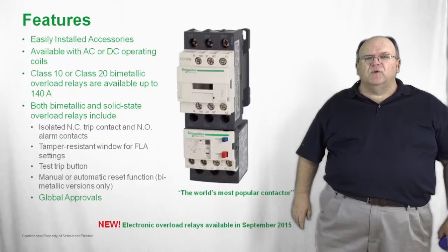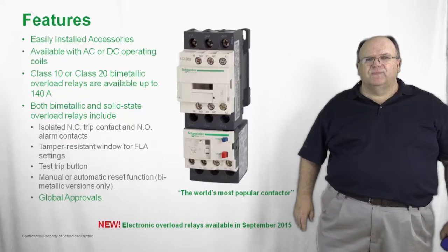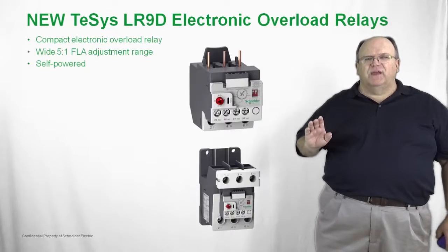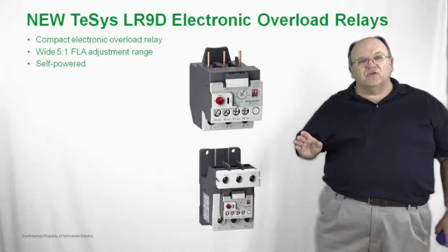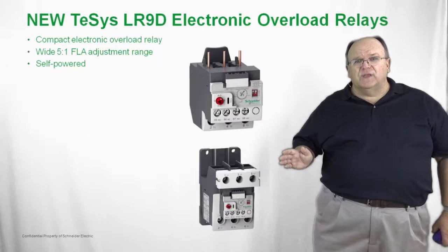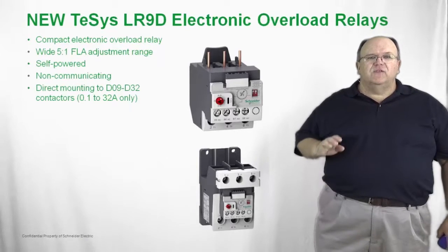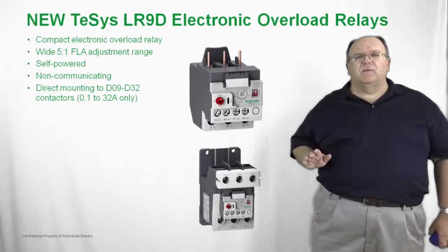In September of 2015, we'll have a complete range of solid state overload relays for the TeSys D family of motor starters. The LR9-D electronic overload relay is a brand new option with a very wide adjustment range — a five to one ratio. This overload relay is self-powered, meaning it does not require any external control voltage to operate. You use the LR9-D the same way you would a bimetallic overload, but with fewer parts, cutting the number of overload relay part numbers in half. It mounts directly to the TeSys D family of contactors from 9 amps up to 32 amps, covering a current range from a tenth of an amp up to 32 amps.